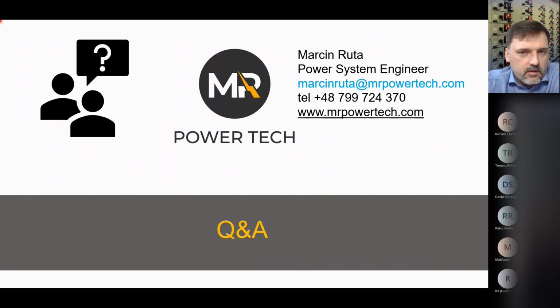I would say it depends what is the purpose for it. Is it protection behind it, or maybe arc flash? Then it means that it's better to use a lockout tagout switch that you can physically lock, or whether just reprogramming digitally is enough. So that's a very interesting topic. I would say it's quite fresh, and combined with GOOSE messaging and IEC 61850, I remember we did a few data centers like this, and it was very interesting. Also challenging, but very interesting to have. Yeah, thank you, Franz.